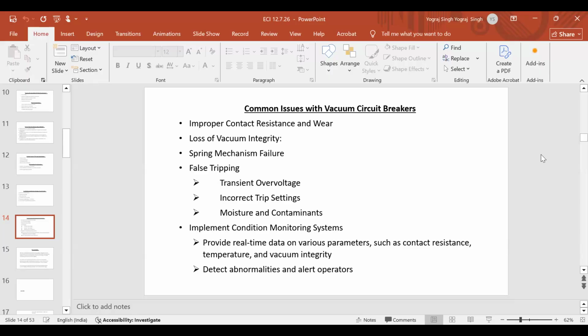So what will happen in case of VCB? Suppose because of prolonged trippings, the vacuum inside has been disturbed. Then there will be a problem of failure. Then the spring mechanism inside it, a very small 4 mm or 5 mm gap, is closed through a strong spring mechanism which is required to be checked. Transient over voltages, incorrect trip settings.